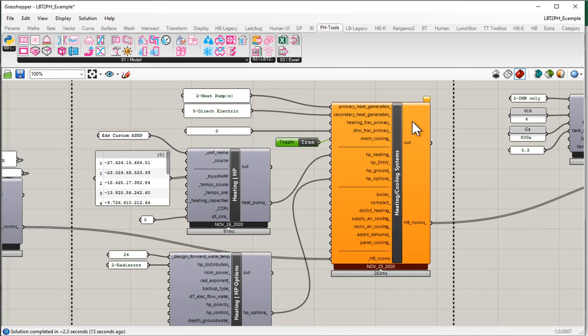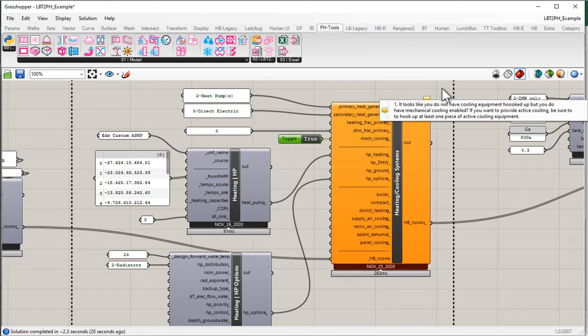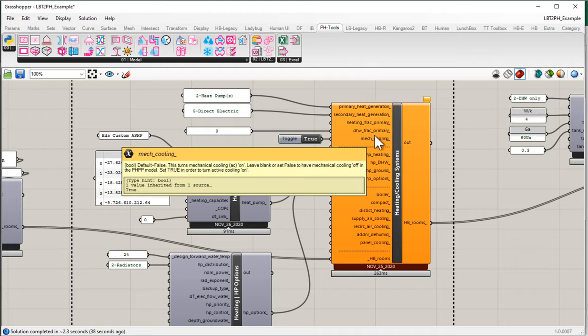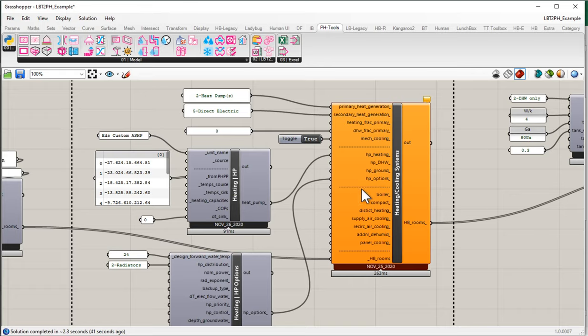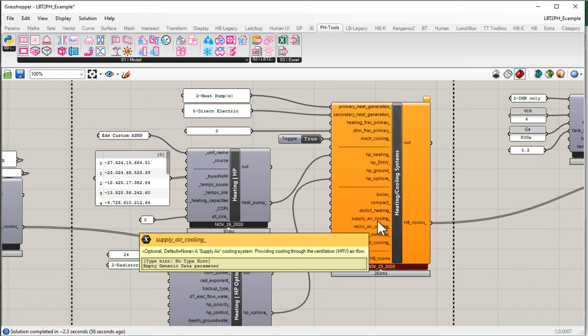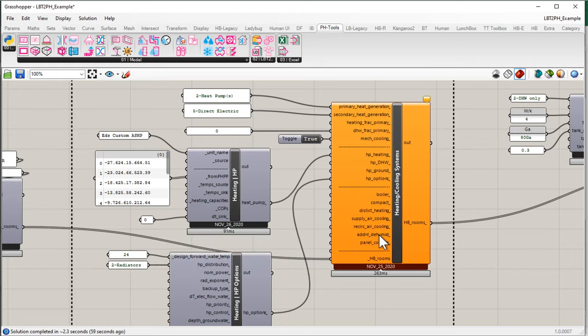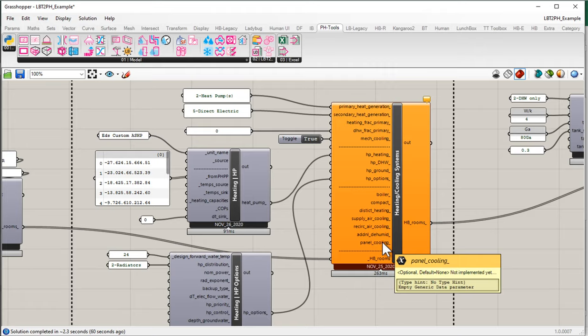So pretty straightforward — there's really not much we need to do there. Notice though we did get some errors. As soon as we turned on mechanical cooling, we got this warning. It says: it looks like you do not have cooling equipment hooked up, but you do have mechanical cooling enabled. If you want to provide active cooling, be sure to hook up at least one piece of active cooling equipment. What it means is: you turned mechanical cooling on, but you didn't actually give me any air conditioning equipment to use. So we need to provide some type of cooling and dehumidification equipment — either supply air cooling, recirculated air cooling, dedicated dehumidification, or radiant cooling.